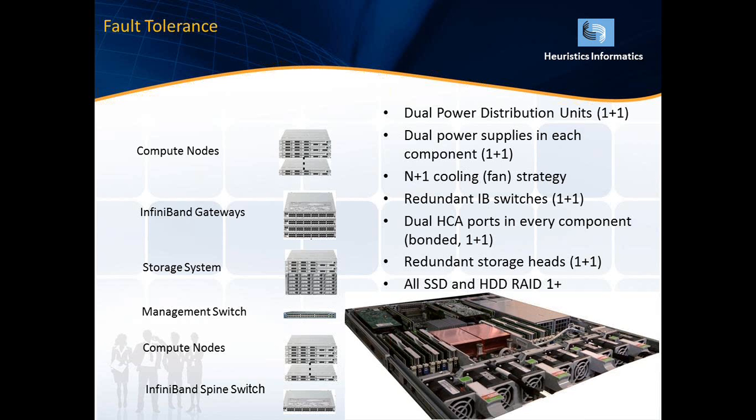In the same way, for each and every component I have power supplies, like the SMPS in each and every standalone desktop. We have two power supplies in each component. The components are the compute nodes, gateway switches, storage system, management switch, and InfiniBand spine switch. Each and every component has two power supplies. Even if one power supply fails, the component will survive with the other. I also have an N+1 cooling fan strategy.